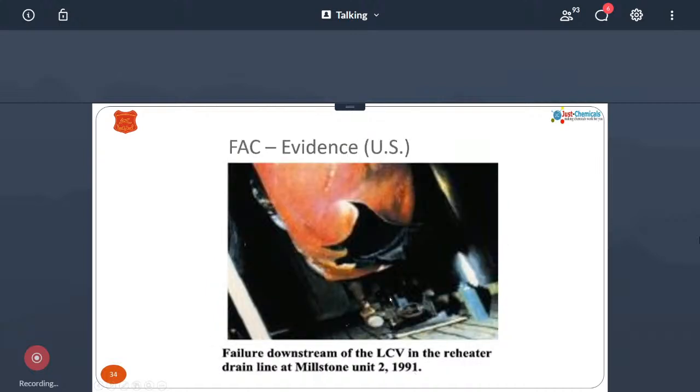And slowly, now people have converted to oxidation treatment, AVTO or OT. Now 70% of NTPC plants have recently, in the last 2-3 years, converted to AVTO, and most of the supercritical plants except 2 of them are in oxidative treatment, and others are still in AVTO because they do not have a good plant load factor to run.